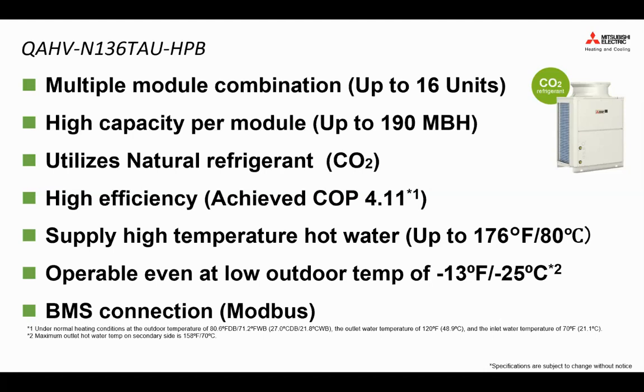So you can supply high temperature hot water up to 80 degrees C, and you can operate down to minus 25 degrees C. You can also have BMS connection to control it through Modbus or through an external signal, 0 to 10 volt, on and off, and temperature setting. And then we're going to go through it in a little more detail in the upcoming slides.